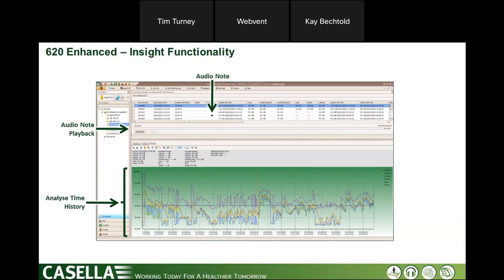You can add exclusion zones, and the tabular data above the graph shows all recalculated values from those zones. Right-clicking in most places gives the same menu options for ease of use. If an audio note is present, a speaker icon appears with a playback bar so you can listen back — for example, to hear who was measured, what they were doing, their job role, duration of noise exposure, or what noise control measures were already in place.